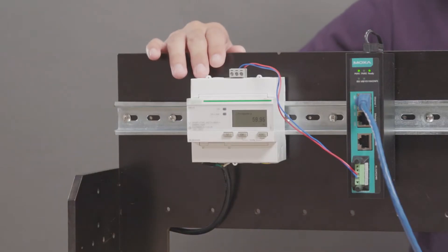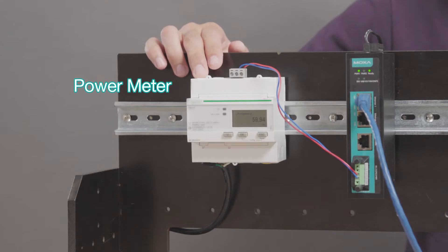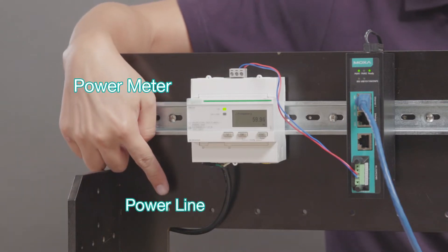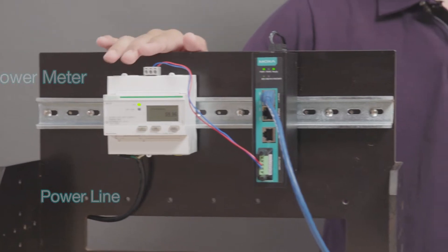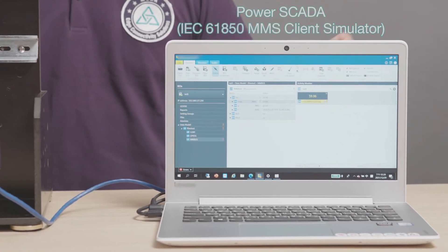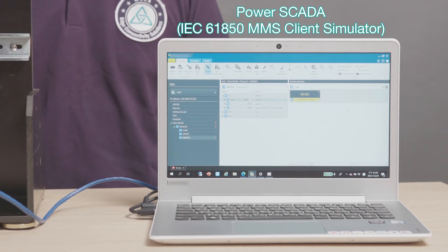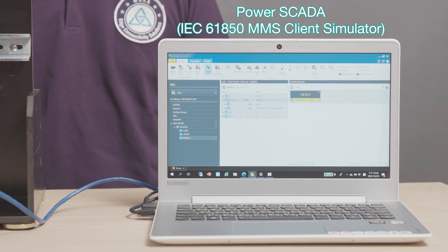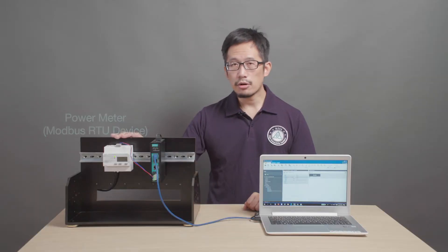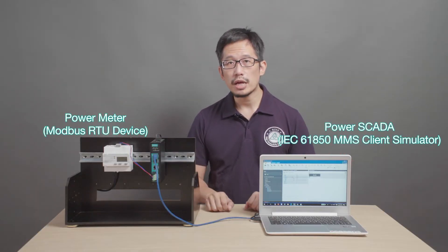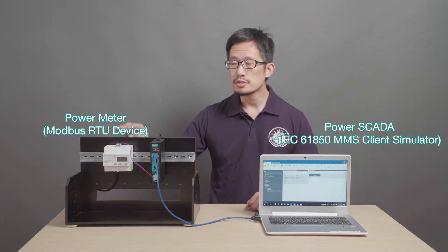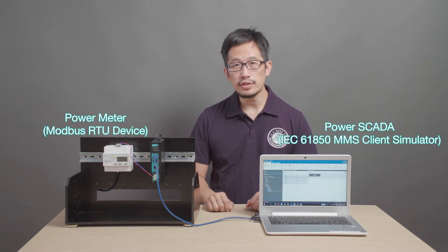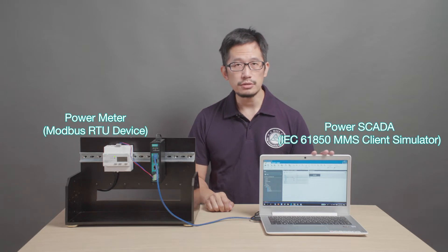Here, we have a power meter that's measuring the usage and quality of power being delivered through this power line. And we want to monitor this power meter in a power SCADA. For this demo, we're using an IEC 61850 MMS client simulator to represent our power SCADA.